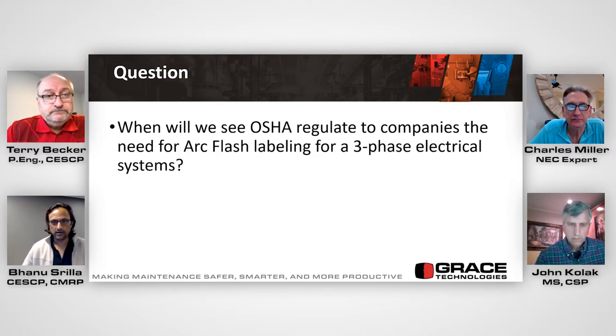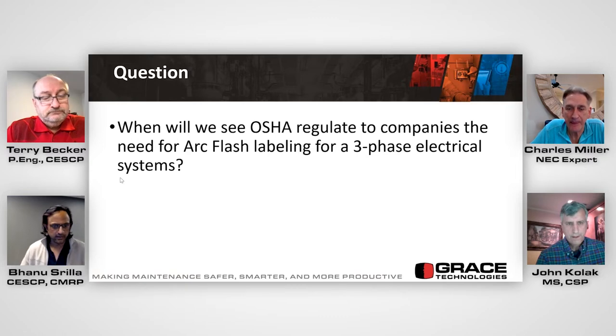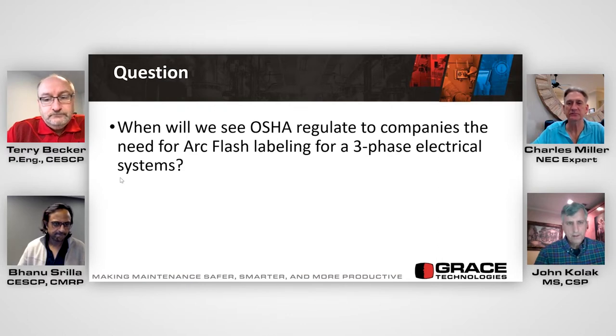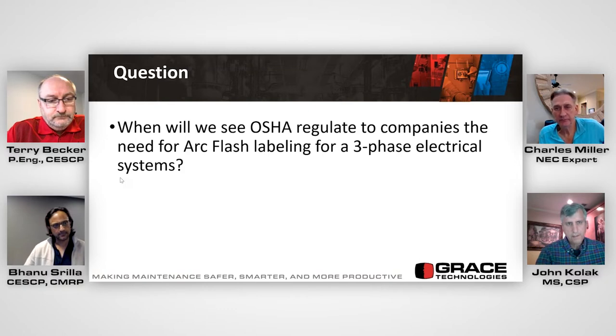This one's for John. When will we see OSHA regulate companies on the need for arc flash labeling for three-phase electrical systems? Well, they already do that via the 70E actually. It's already a requirement to do a hazard analysis, and among other things, the labeling requirements in the 70E apply here. So if it's going to be accessed in the field for maintenance or troubleshooting, it needs a label on it. OSHA already says they'll defer to that.